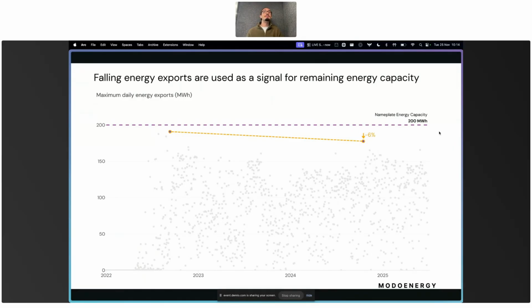The reason I say it's an overestimation is that this could be for a number of different reasons. Part of it could be attributed to actual physical degradation in the cell chemistries of the battery. But it could also be due to recoverable losses, like cell imbalances. If the state of charge across the cells of the battery rack differs, that puts an artificial limit on the total energy capacity, and these can be recovered through rebalancing of cells.